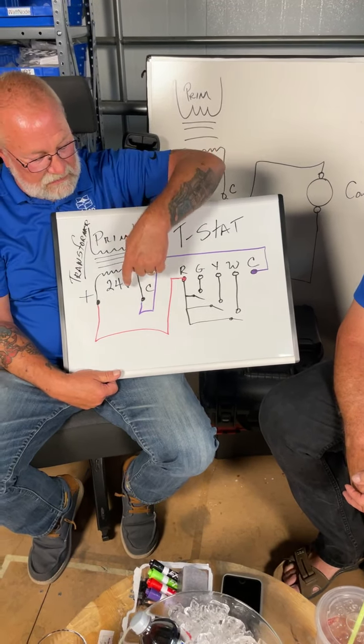So you have a series of switches. When your thermostat calls for cooling, then the Y will close and the G will close. G brings on the fan, Y should bring on the condensing unit. So I broke that down a little bit further. I'm going to give this to Michael.